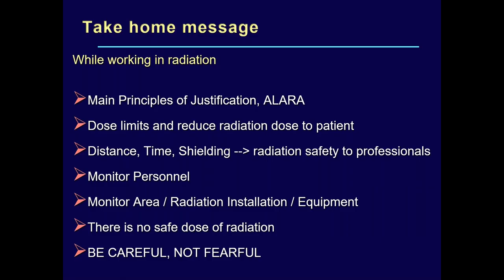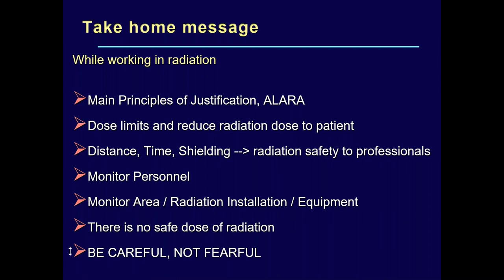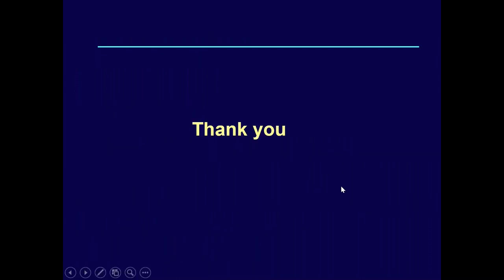The take-home message from this lecture: radiation use must be justified — the benefit must be larger than the risk. Always apply the ALARA principle (as low as reasonably achievable). Dose limits must be respected for both patients and radiation staff. Time, distance, and shielding are all equally important and together optimize radiation protection. Maintain personal and area monitoring systems. Understand that there is no absolutely safe dose of radiation — so be careful, but not fearful.